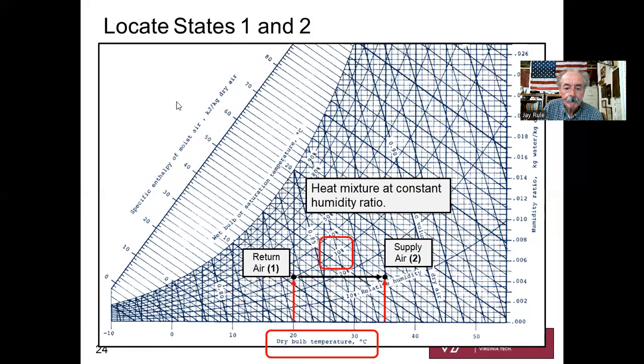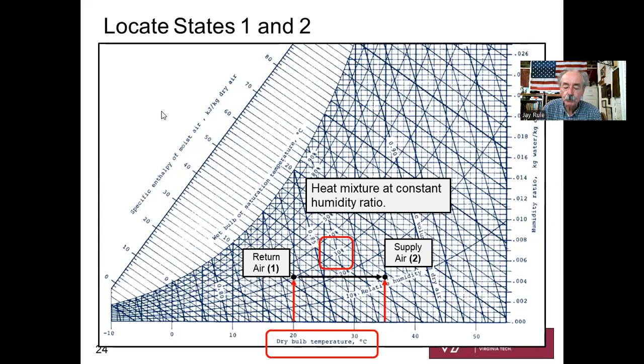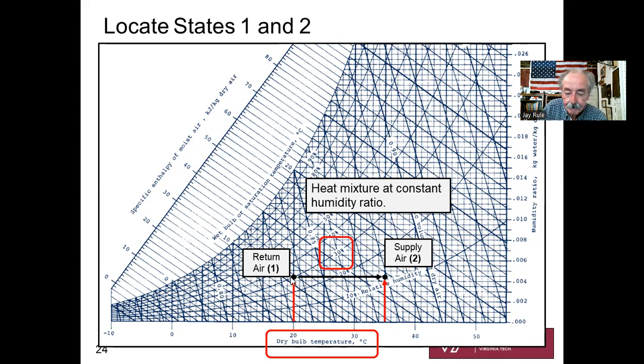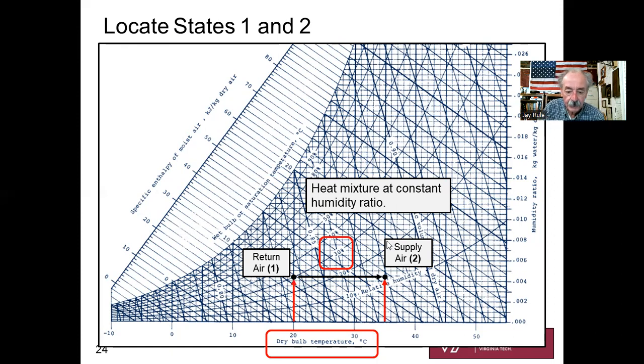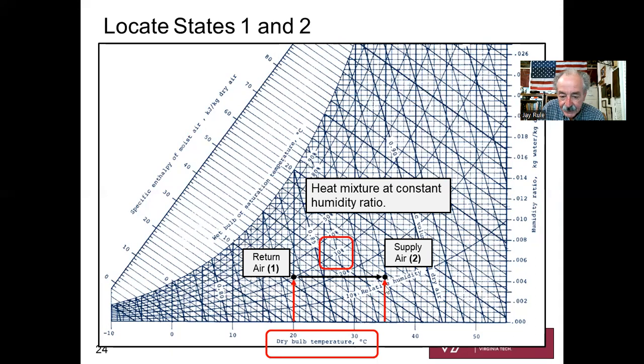We plan to locate states one and two on the psychrometric chart. State one: dry bulb temperature 20°C and relative humidity 30% — we find where these lines intersect and place a dot. Since we're heating at constant humidity ratio — dry air flow and vapor flow are both constant — we move horizontally to 35°C for state two and place another dot. That horizontal line is our heating process.